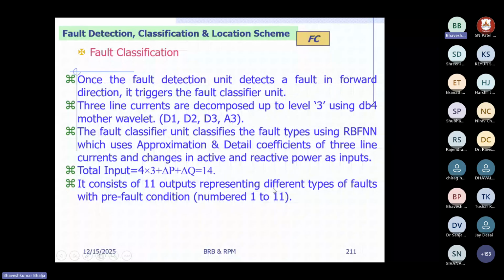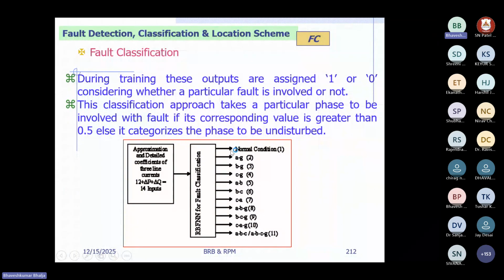And then you can consider the fault classification. Once you have the wavelet output, you can give it, normalized of course, as features. Then you can define the fault classification algorithm output like this: one is normal condition, two is line A to ground or R to ground, Y to ground, B to ground, and so on. So likewise, you can give the numbers 1 to 11, and depending upon the output, the utility person knows that this is the type of fault which has occurred.